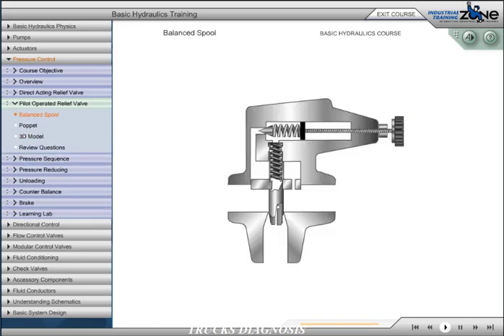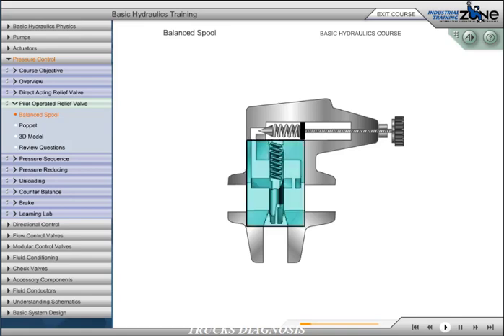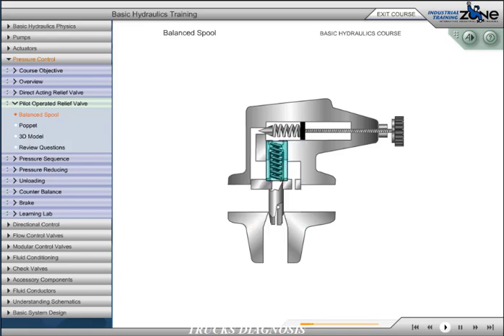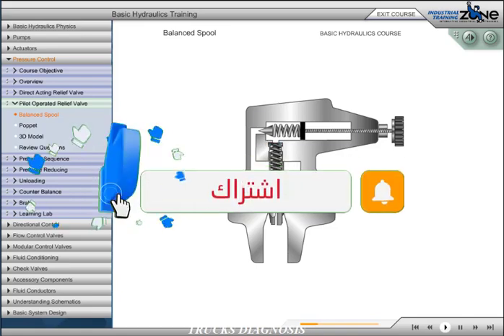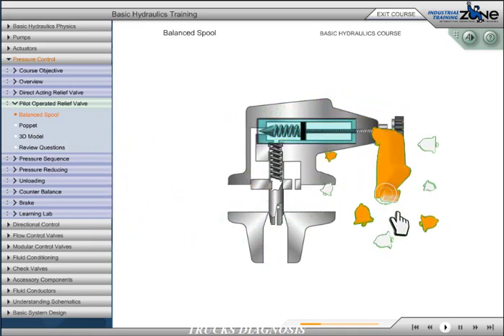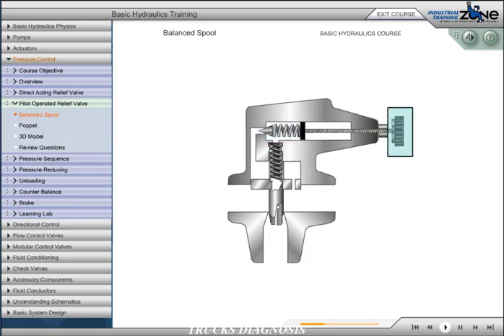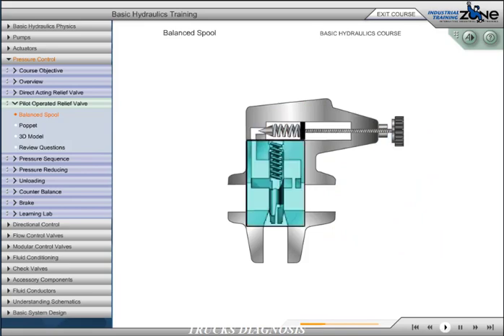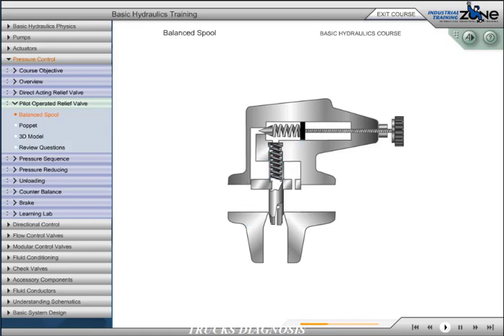The pilot operated relief valves are designed to accommodate higher pressures with higher flows in smaller frame sizes than direct acting relief valves. The valve is built in two stages. The second stage includes the main spool held in a normally closed position by a light, non-adjustable spring, and is large enough to handle maximum flow. The first stage is a small direct acting relief valve mounted as a crosshead on the main valve body, and includes a poppet, spring, and adjustable knob. The second stage handles full rated flows to tank. The first stage controls and limits pilot pressure level in the main chamber.